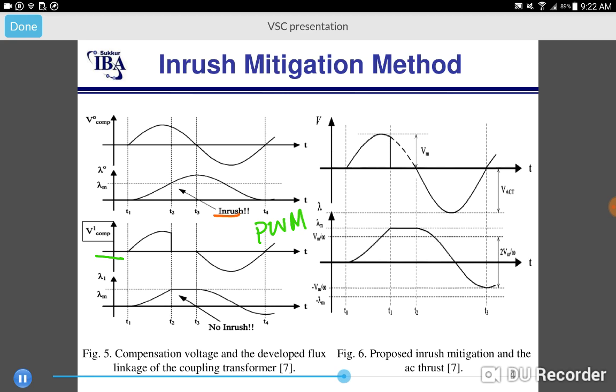Here the compensated voltage is injected at T is equal to T1. As the projected flux reaches the maximum flux, you can see here at T is equal to T2, the risk of high inrush current appears. In this scheme, the original compensated voltage is cut off during the time T2 to T3. In this way, the flux does not reach the maximum point and the inrush current is reduced. However, although this technique successfully reduces the inrush current, you can see here at the output waveform, the quality of the voltage at the output is being compromised.